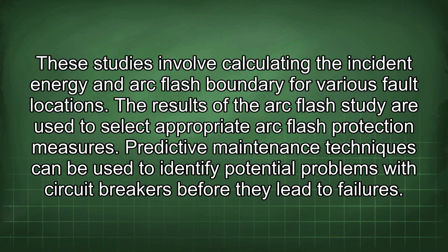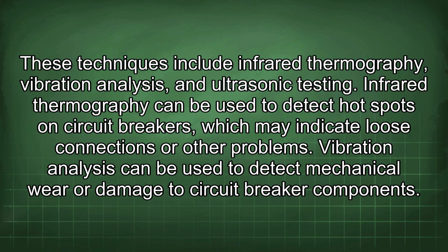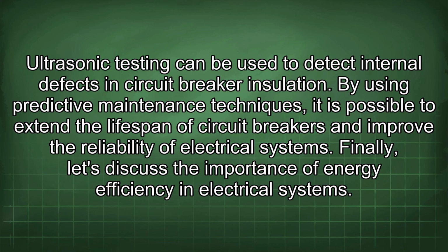Predictive maintenance techniques can be used to identify potential problems with circuit breakers before they lead to failures. These techniques include infrared thermography, vibration analysis, and ultrasonic testing. Infrared thermography can be used to detect hotspots on circuit breakers, which may indicate loose connections or other problems. Vibration analysis can be used to detect mechanical wear or damage to circuit breaker components. Ultrasonic testing can be used to detect internal defects in circuit breaker insulation. By using predictive maintenance techniques, it is possible to extend the lifespan of circuit breakers and improve the reliability of electrical systems.